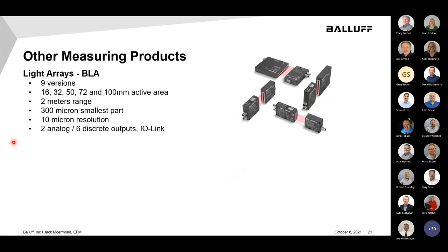Another big one for Balluff, one that sets us apart from the competition, are the BLAs, the light arrays. As I mentioned before, we released the new family of these. They go from 16 millimeter active areas up to 100 millimeter active areas. You can put these up to 2 meters apart, but remember, when you put these 2 meters apart, your resolution is affected, and all of that's laid out in the manual.